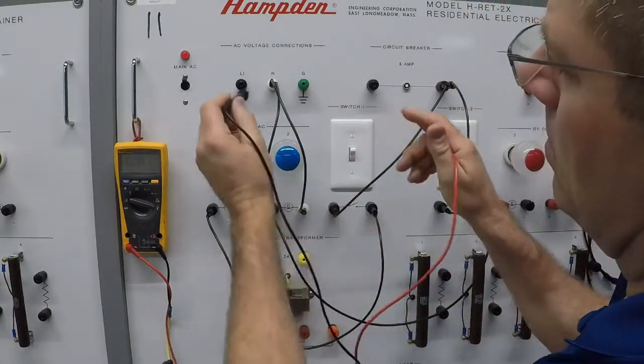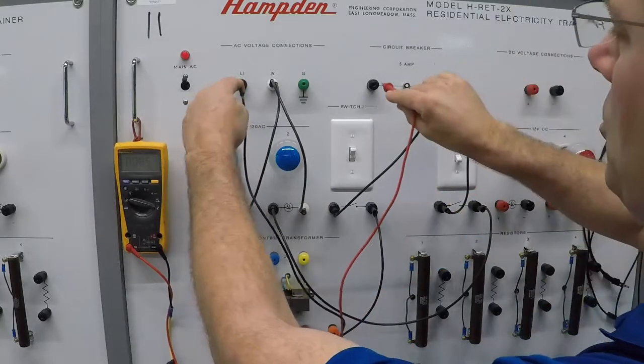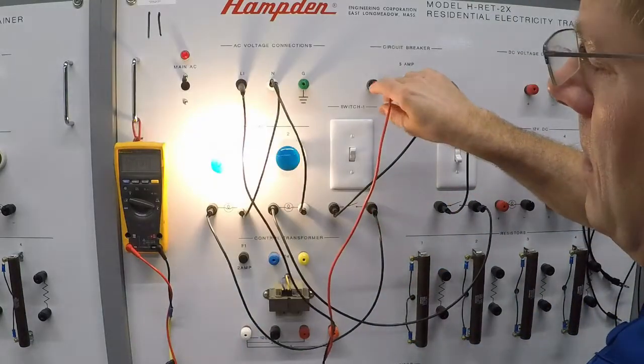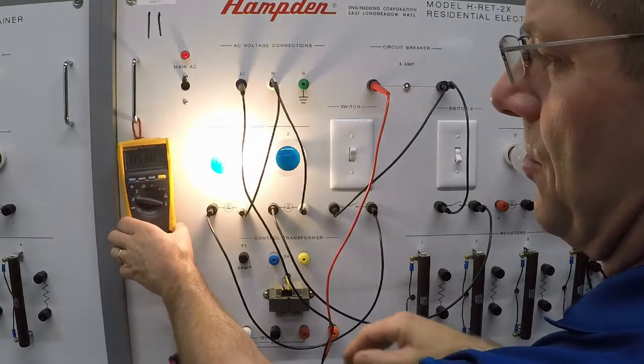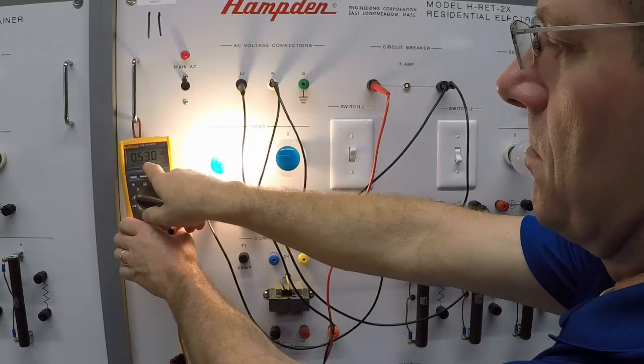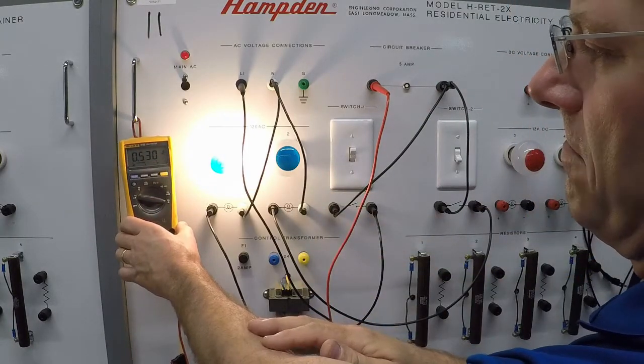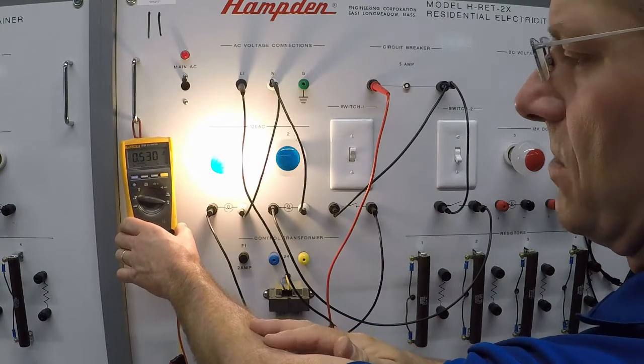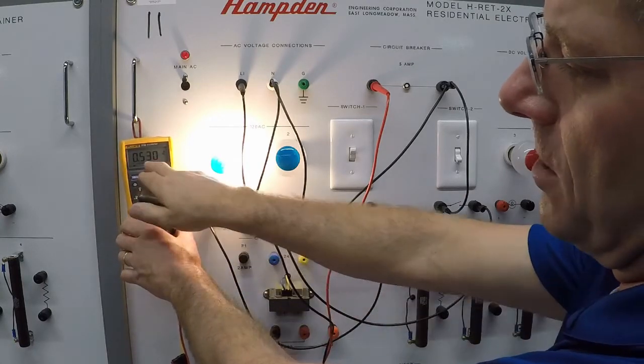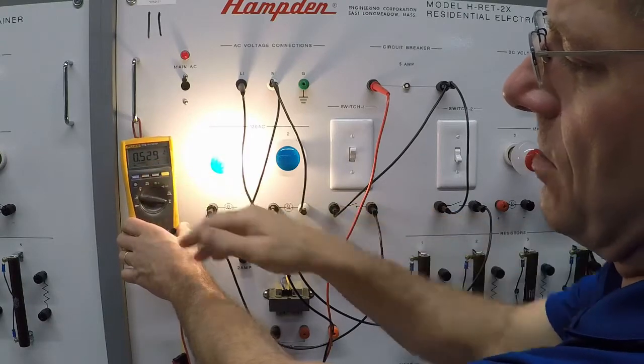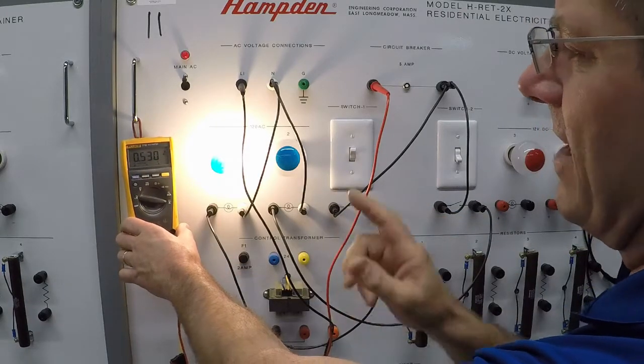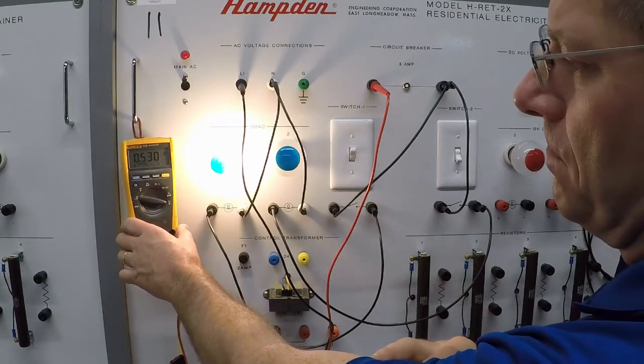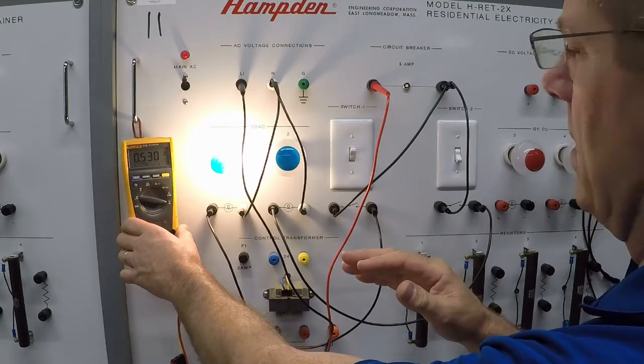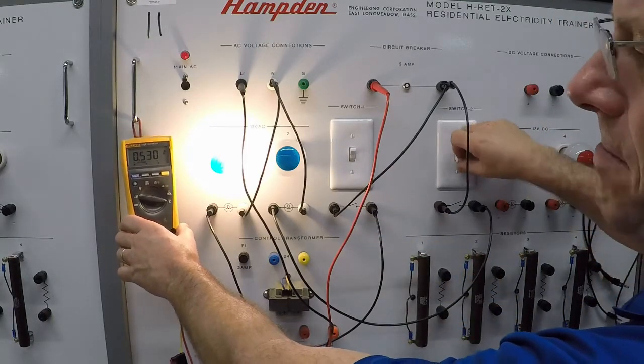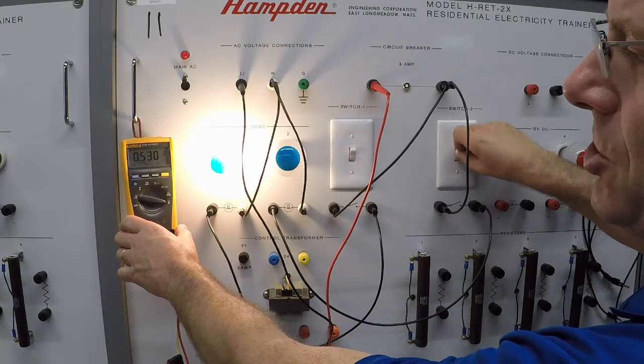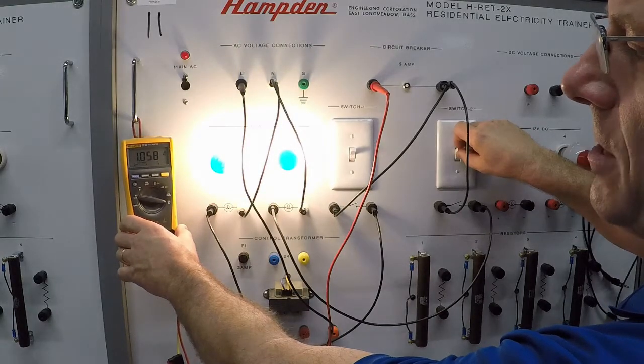We will measure from L1 to our circuit breaker, and you'll notice it's approximately the same. 0.526 was our current before. It is 0.530 now. That is IT. That is IT.